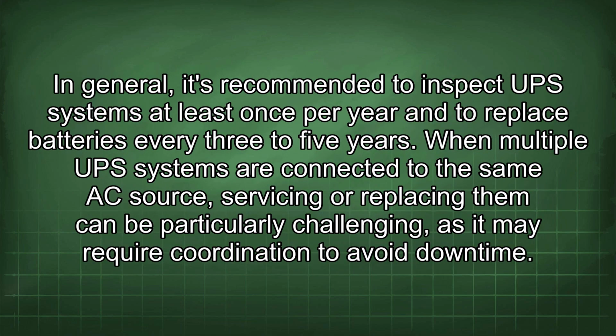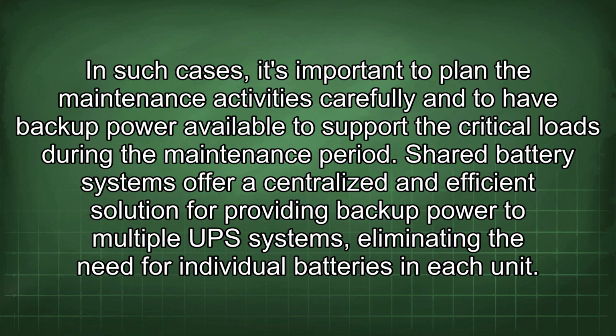In general, it's recommended to inspect UPS systems at least once per year and to replace batteries every 3 to 5 years. When multiple UPS systems are connected to the same AC source, servicing or replacing them can be particularly challenging, as it may require coordination to avoid downtime. In such cases, it's important to plan the maintenance activities carefully and to have backup power available to support the critical loads during the maintenance period.